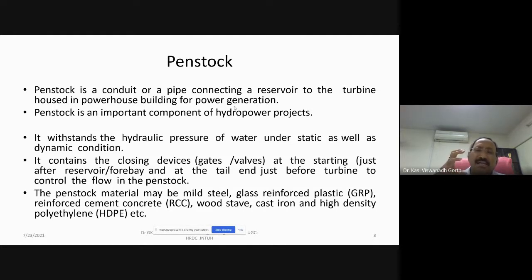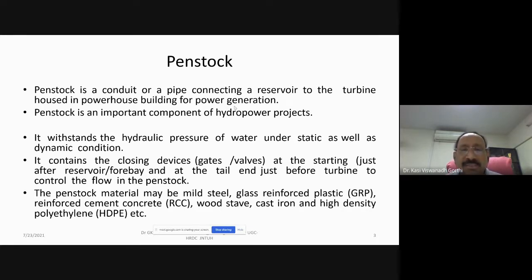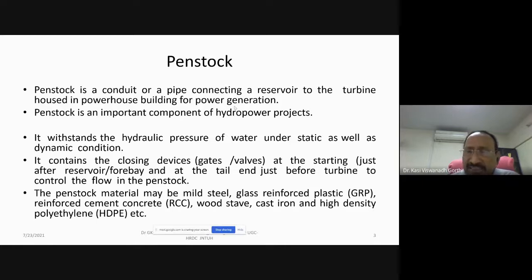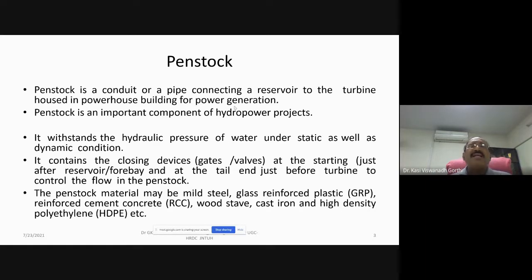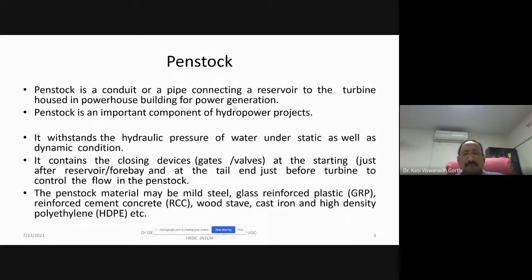The design of penstock is a very important topic because the penstock pipe carries water under pressure — if the pressure is more, the penstock bursts. So you need to be very careful while taking up the design. It should withstand the hydraulic pressure of water under static as well as dynamic conditions. It contains closing devices like gates and valves at the start just after the reservoir and at the tail end just before the turbine to control the flow in the penstock. The penstock material may be mild steel, glass reinforced plastic (GRP), reinforced cement concrete, wood stave, or even cast iron.